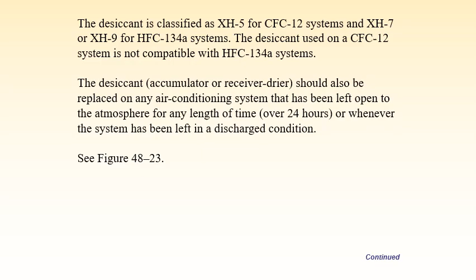Here you can see this one is the receiver dryer in the case of this expansion valve system. It takes the vapor inlet. This filter pad removes any foreign particles, and this desiccant removes the moisture, and then it supplies through this tubing. This is the inside tube. From this tube it goes to the outlet. There is a sight glass here. In this glass you can see the condition of the refrigerant. This is used in the expansion type of system, and this is used on the high side.